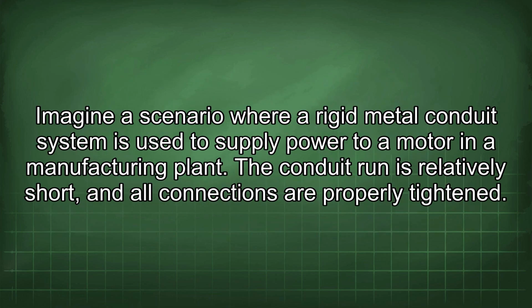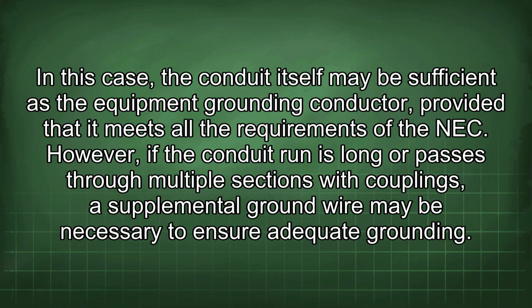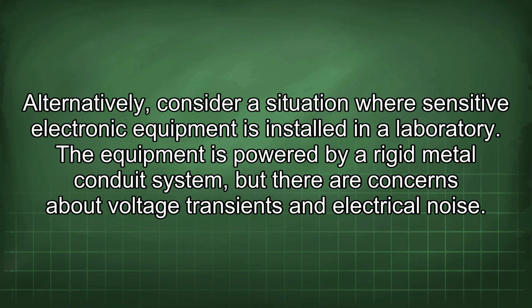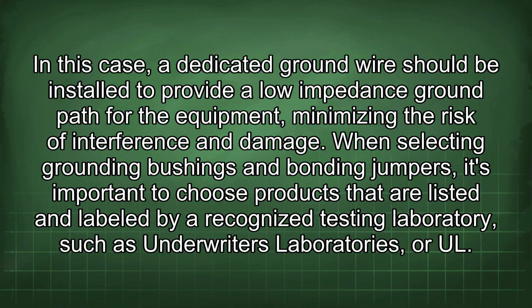Imagine a scenario where a rigid metal conduit system is used to supply power to a motor in a manufacturing plant. The conduit run is relatively short, and all connections are properly tightened. In this case, the conduit itself may be sufficient as the equipment grounding conductor, provided that it meets all the requirements of the NEC. However, if the conduit run is long or passes through multiple sections with couplings, a supplemental ground wire may be necessary to ensure adequate grounding. Alternatively, consider a situation where sensitive electronic equipment is installed in a laboratory. The equipment is powered by a rigid metal conduit system, but there are concerns about voltage transients and electrical noise. In this case, a dedicated ground wire should be installed to provide a low impedance ground path for the equipment, minimizing the risk of interference and damage.